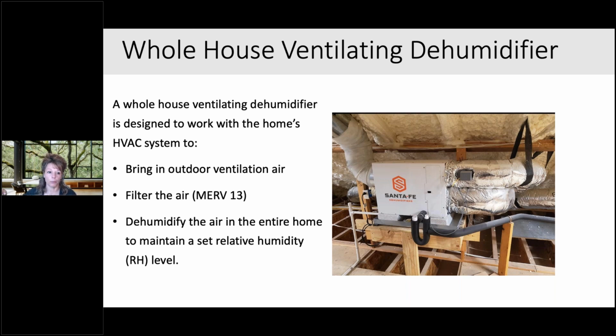And it's designed to bring in outdoor ventilation air. So we're a supply ventilation strategy to try to put that slight positive pressure, especially for mixed humid and humid climates. That's important. We filter with a MERV 13 filter, and we dehumidify all the air in the home independent of the AC system. And this is what an install would typically look like when utilizing that outdoor ventilation air. You don't have to. If they're using another ventilation strategy and they don't want to use the dehumidifier for the ventilation, there's a damper in there and you just cap that right off.